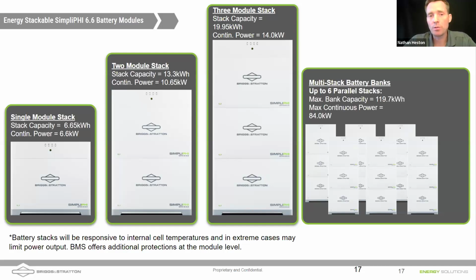For a 12K Sol-Ark, for instance, you would want a minimum to be able to take advantage of that 9 kilowatts of battery power to load of a 12K — you'd want to go with a minimum of a 2 battery module stack. So a stack, just to let everybody know, consists of a base — it could be a wall mount base or a floor base — then a number of battery modules, could be 1 up to 3, and then a controller that sits on top. That stack controller communicates with each of the individual battery modules and then communicates out with that Sol-Ark inverter.